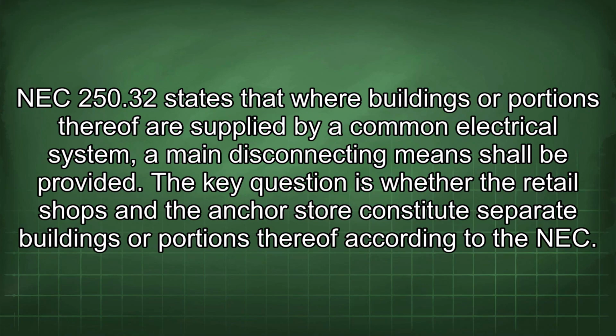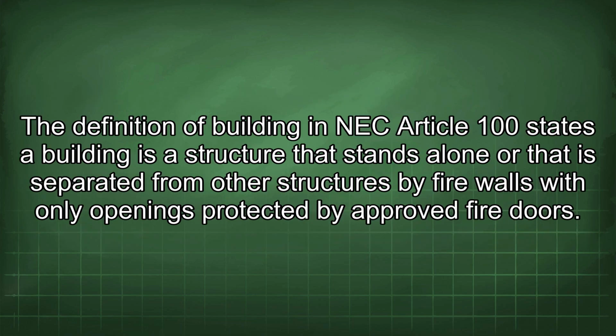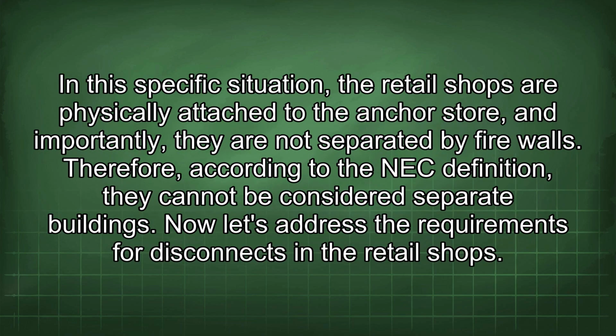NEC 250.32 states that where buildings or portions thereof are supplied by a common electrical system, a main disconnecting means shall be provided. The key question is whether the retail shops and the anchor store constitute separate buildings or portions thereof according to the NEC. The definition of building in NEC Article 100 states a building is a structure that stands alone or that is separated from other structures by fire walls with only openings protected by approved fire doors. In this specific situation, the retail shops are physically attached to the anchor store, and importantly, they are not separated by fire walls. Therefore, according to the NEC definition, they cannot be considered separate buildings.